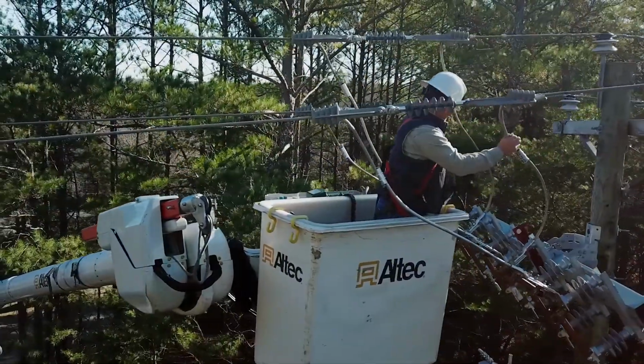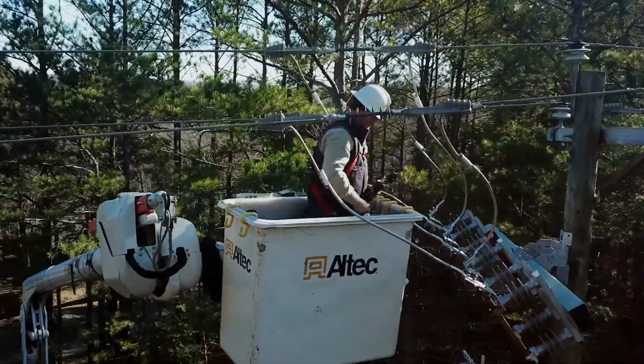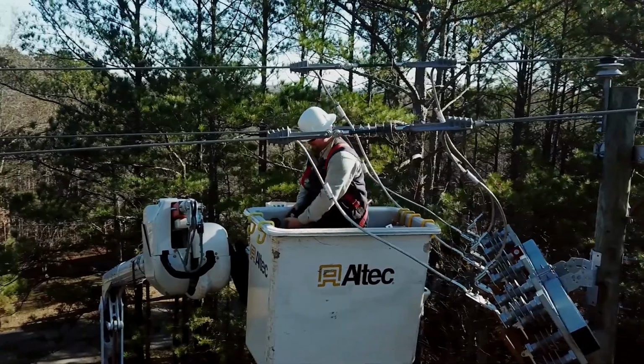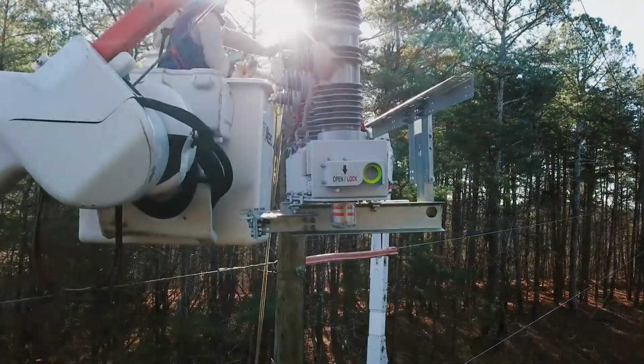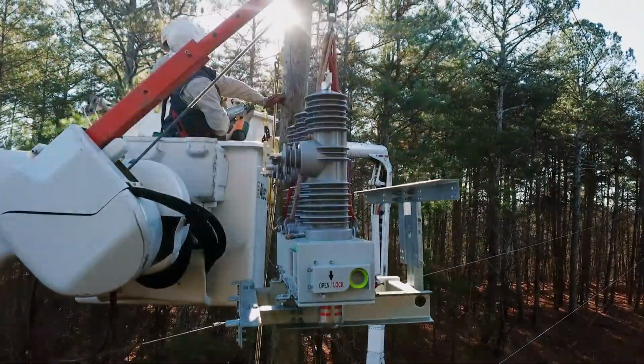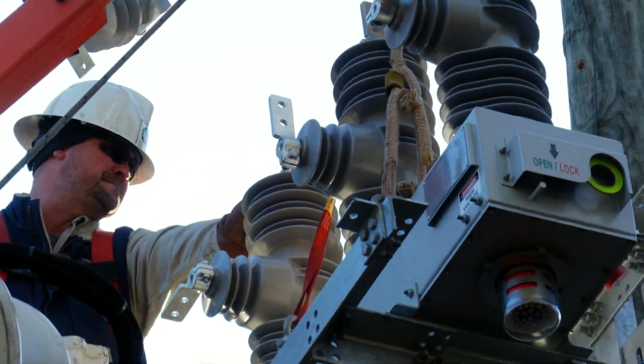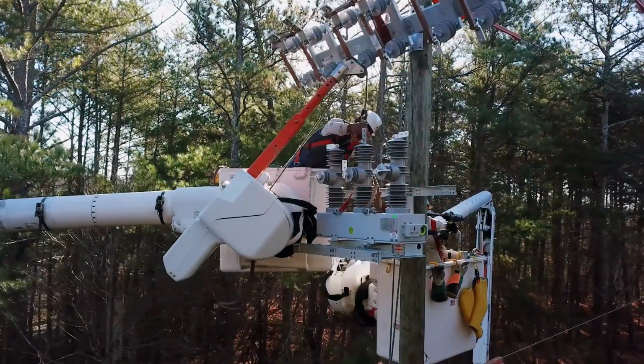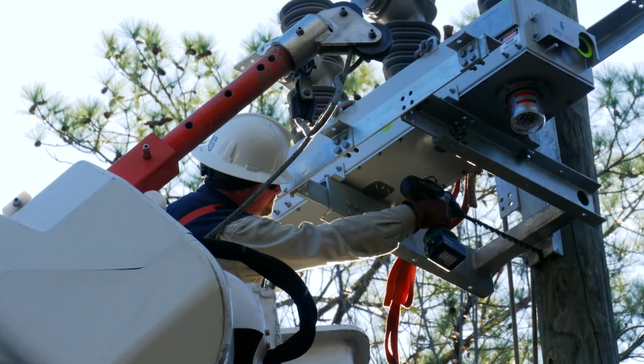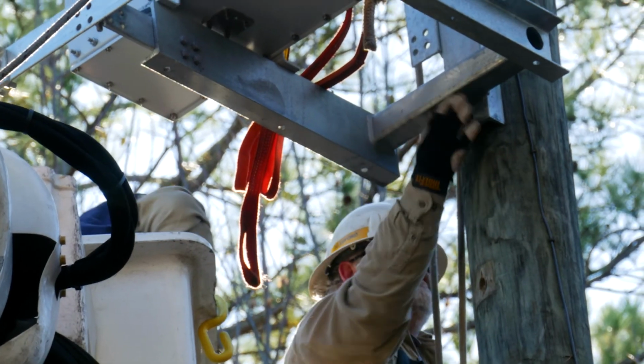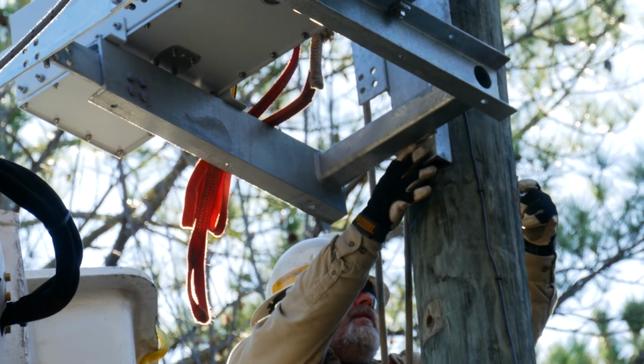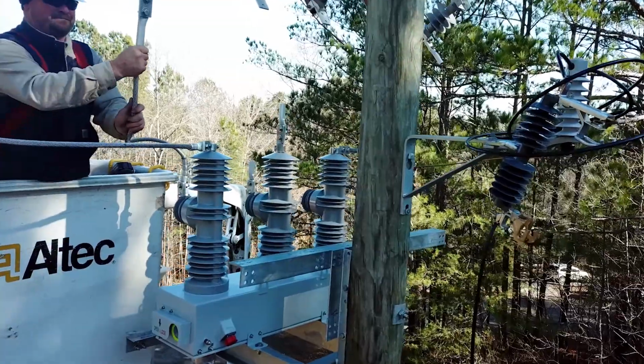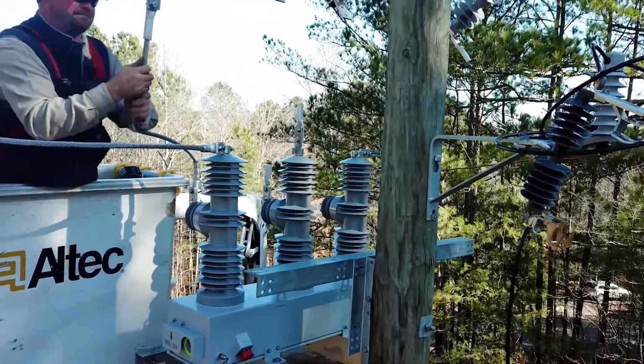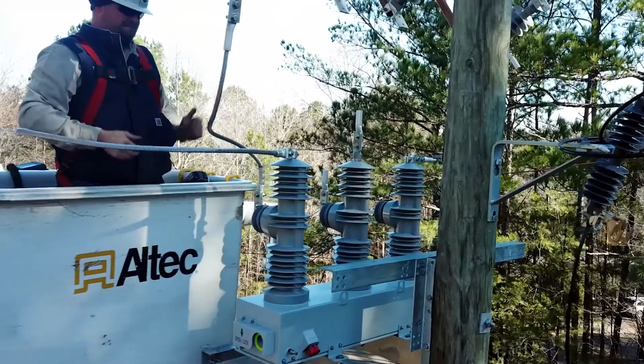With the line dead-ended and jumpers run down to the bypass switches, it is now time to proceed with the mounting of the recloser. The Southern States Recloser, which is light enough to be lifted with the material handler on a bucket, is placed on the pole and bolted into place per the guidelines specified in the instruction manual. With the recloser mounted, the utility then runs the jumpers from the bottom of the disconnect switches to the recloser.